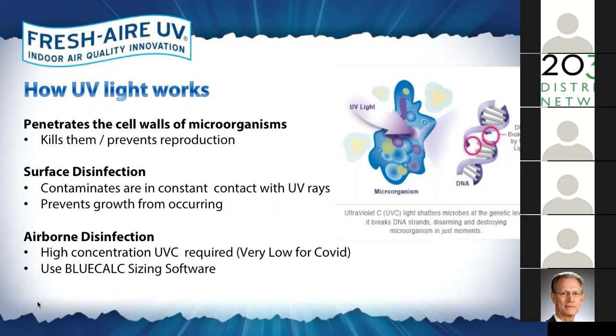So for surface disinfection with UV, you've got an unlimited amount of time, and we've been using that application of coil and drain pan irradiation for many years to keep those areas completely sterilized. Now with COVID, people are all asking for airstream or airborne disinfection. And normally that is very difficult because a lot of bugs require a lot of energy. We're very lucky that COVID requires a very low dosage of energy. So we can actually use a BlueCalc sizing software and create an array of UV that is actually cost effective, while also keeping your coil and drain pan clean for energy benefits.